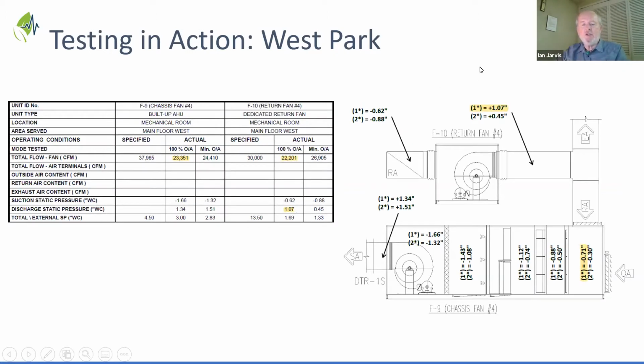So in this case, just to make it a bit more readable, we've colored in test scenario 1, which is the 100% outside air test. So this is a recirculating system. You can see the recirculation air and the exhaust air, the recirc going down, the exhaust air going up. So these would always be tested at 100% air, which is the free cooling mode, which is a relatively short period of time in this climate.